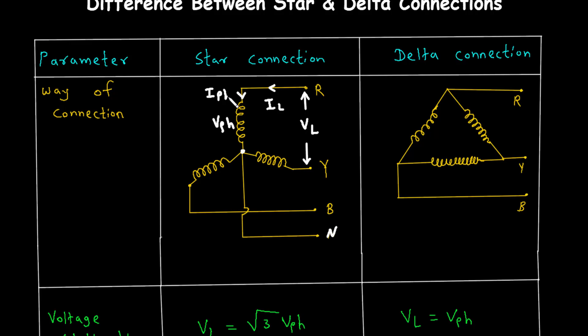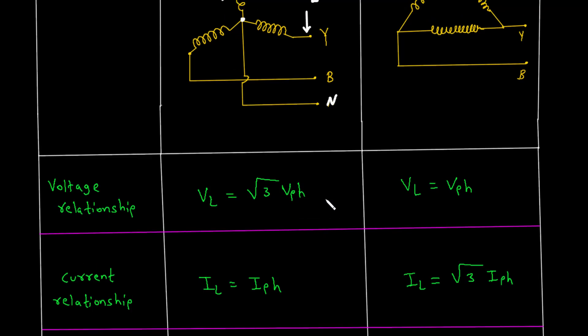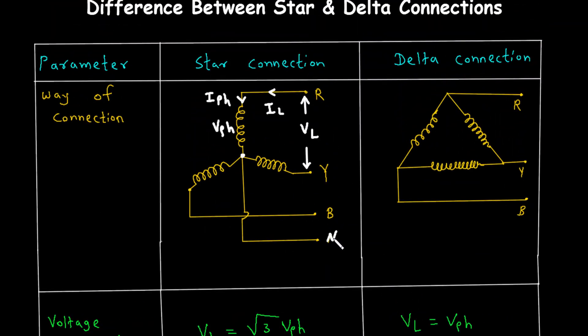An important feature of the star connection is the neutral point. This point can be connected to the ground for safety and stability. It provides a return path for unbalanced currents. This is particularly useful in power distribution networks, where having a neutral point helps manage loads that aren't perfectly balanced.